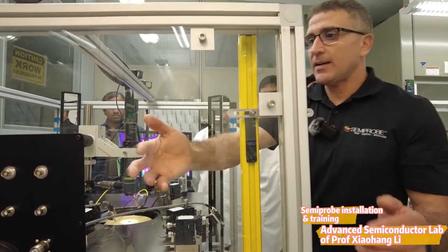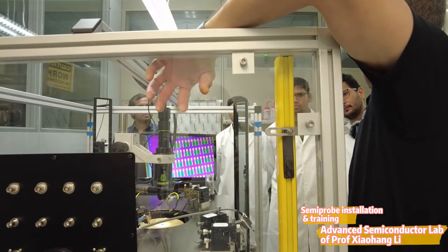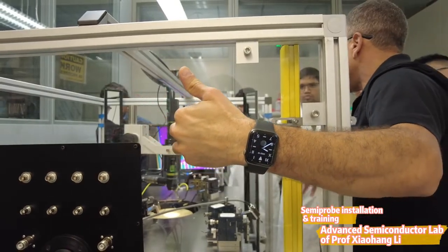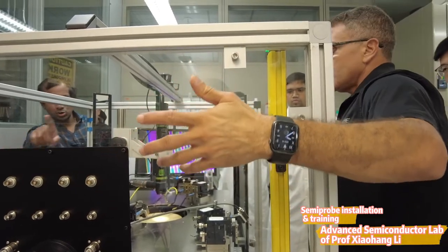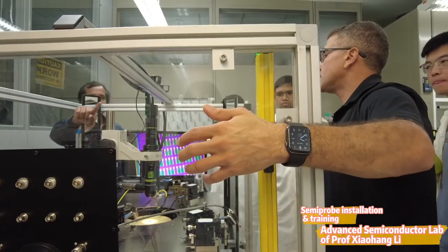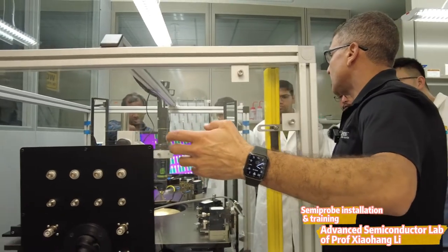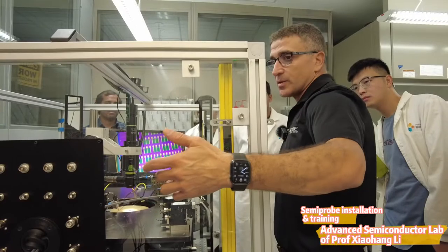On this side, even if you put your hand through, that's why we have the plexiglass — so nobody can put their hands through this area. The idea is you need an area where the cables go for measurements, so this is the blind spot. That window exists because the laser won't travel in that direction. If you take the glass out, it's an issue, so this should not come out.